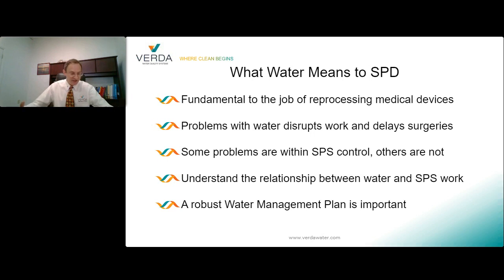It may vary depending on treatments that the local water department is doing to maintain the quality of the municipal water supply, or they may increase the pH to prevent lead from leaching out of aging pipes. When the pH raises above 8.5, if you have an RO system, those membranes are compromised and the product water quality suffers.